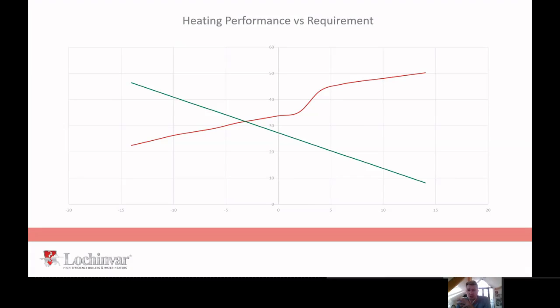The green line that's just appeared on the screen is the load. So that's the nicely selected, appropriately sized air source heat pump. But remember, I called it a 45 kilowatt unit. Well, it's only actually the kilowatt rating that you would require at your design temperature. So whenever you approach a manufacturer for a quotation, if you're a mechanical engineer designing a building, chances are the heat pump looks over-spec'd until you actually look at what it's capable of at our design condition. Always bear that in mind.